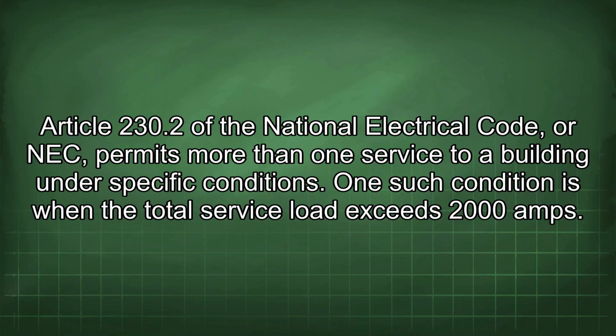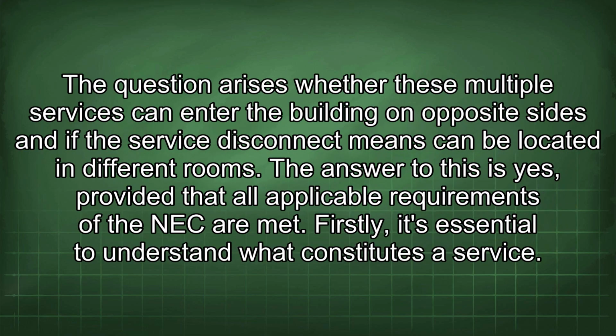Article 230.2 of the National Electrical Code, or NEC, permits more than one service to a building under specific conditions. One such condition is when the total service load exceeds 2000 amps. The question arises whether these multiple services can enter the building on opposite sides and if the service disconnect means can be located in different rooms. The answer to this is yes, provided that all applicable requirements of the NEC are met.